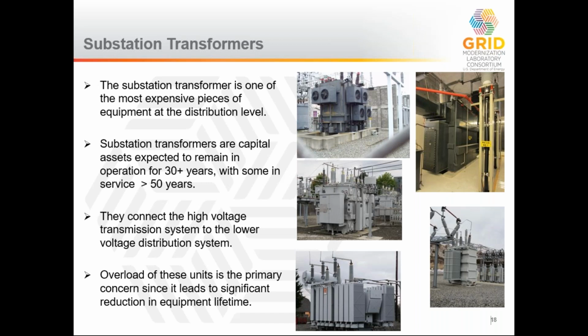And so a lot of the operations around power systems are maintaining voltage, but also looking at what is the loading on the transformers and making sure they stay within their normal operating realm. You can see that these are actually pretty active devices in that the coils themselves are static, but some of these, such as the upper right hand, it's an interior building transformer. The exterior ones can have anything from passive cooling to forced fans to spray cooling. There's a lot of different ancillary systems that are designed to help these operate. Next slide, please.